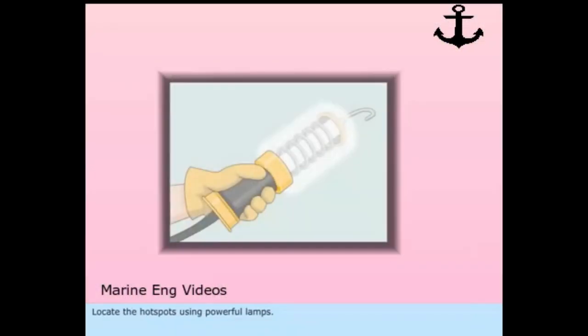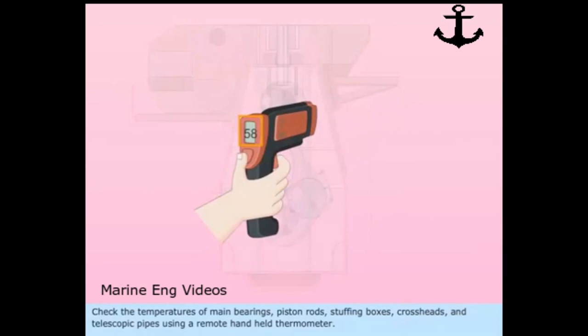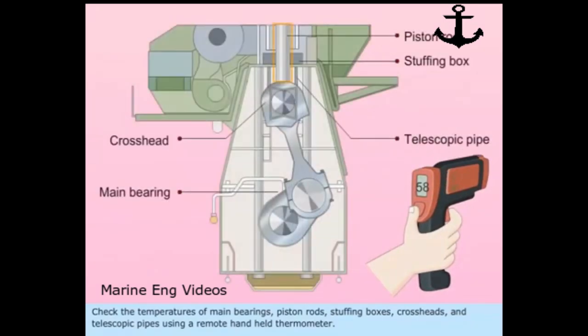Locate the hot spots using powerful lamps. Check the temperatures of main bearings, piston rods, stuffing boxes, crossheads, and telescopic pipes using a remote hand-held thermometer.